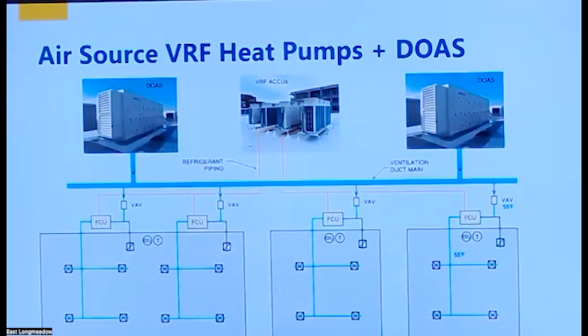And then we have VAV boxes, which throttle that ventilation air depending on the carbon dioxide levels in an individual space. So there's a carbon dioxide sensor on the wall. We give it a set point above which we don't want it to go, and that controls how much ventilation air goes into the classroom. I'm going to show you also a little bit more about some of the pieces and parts of the system in the next couple slides. Next slide, please.